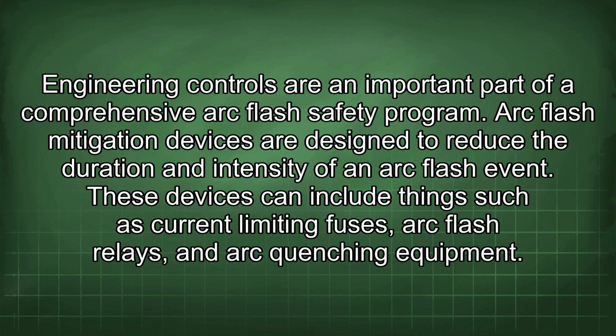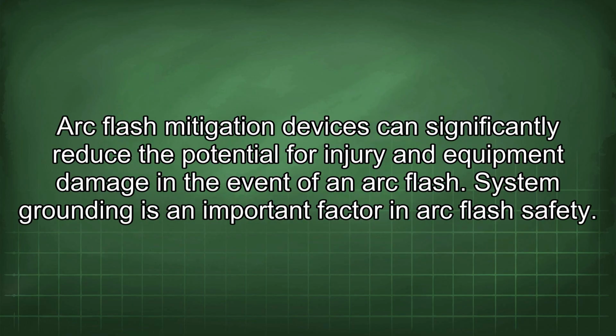Arc flash mitigation devices are designed to reduce the duration and intensity of an arc flash event. These devices can include things such as current-limiting fuses, arc flash relays, and arc quenching equipment. Arc flash mitigation devices can significantly reduce the potential for injury and equipment damage in the event of an arc flash.